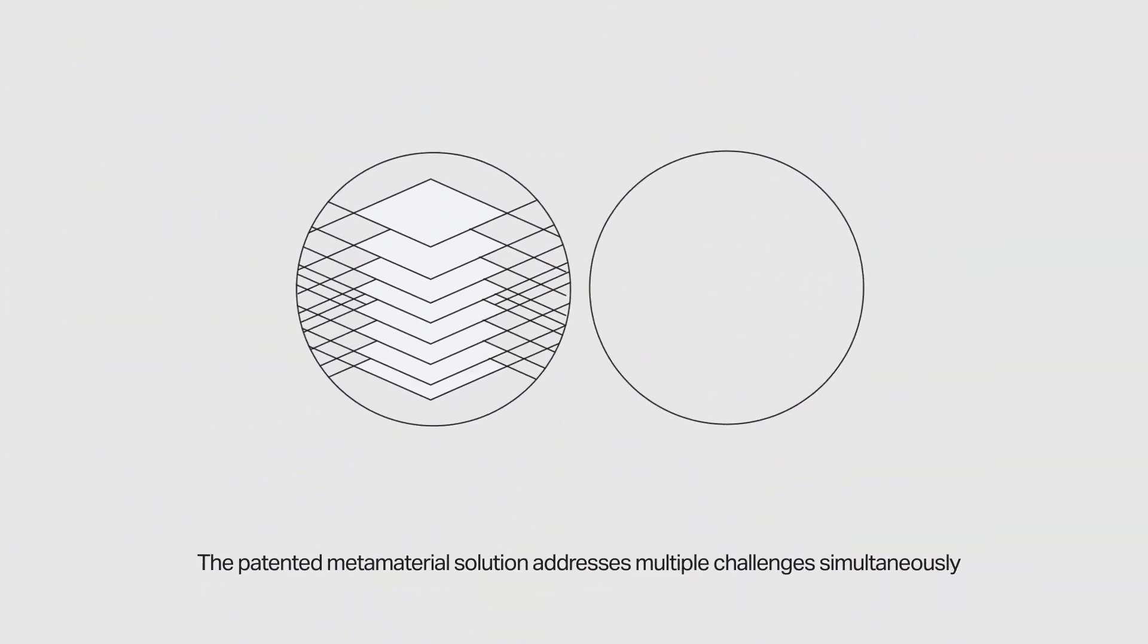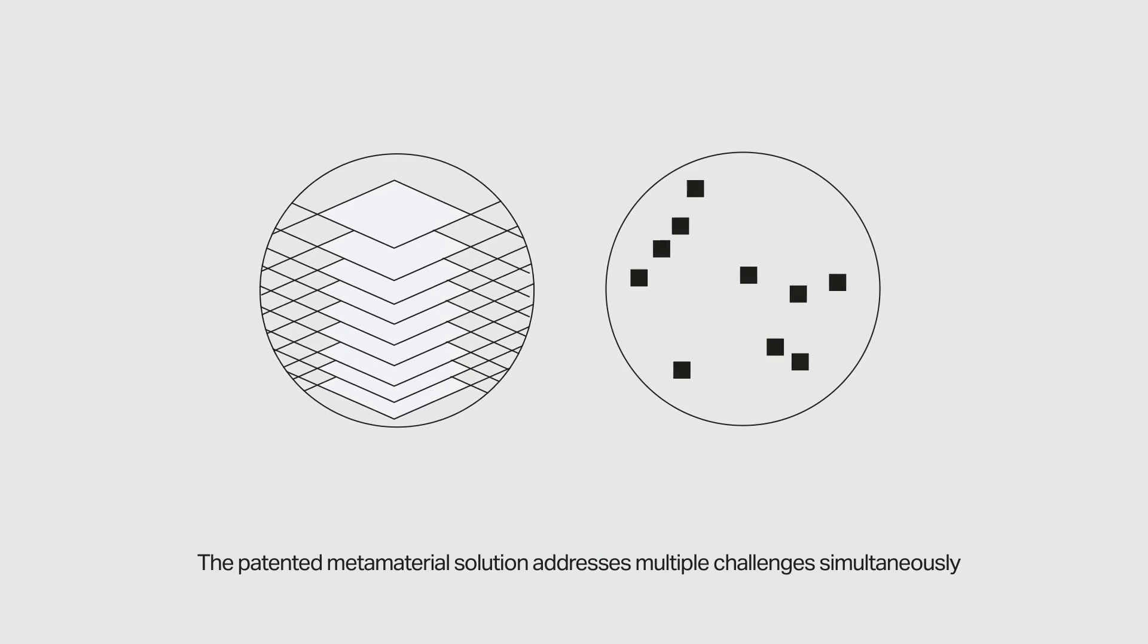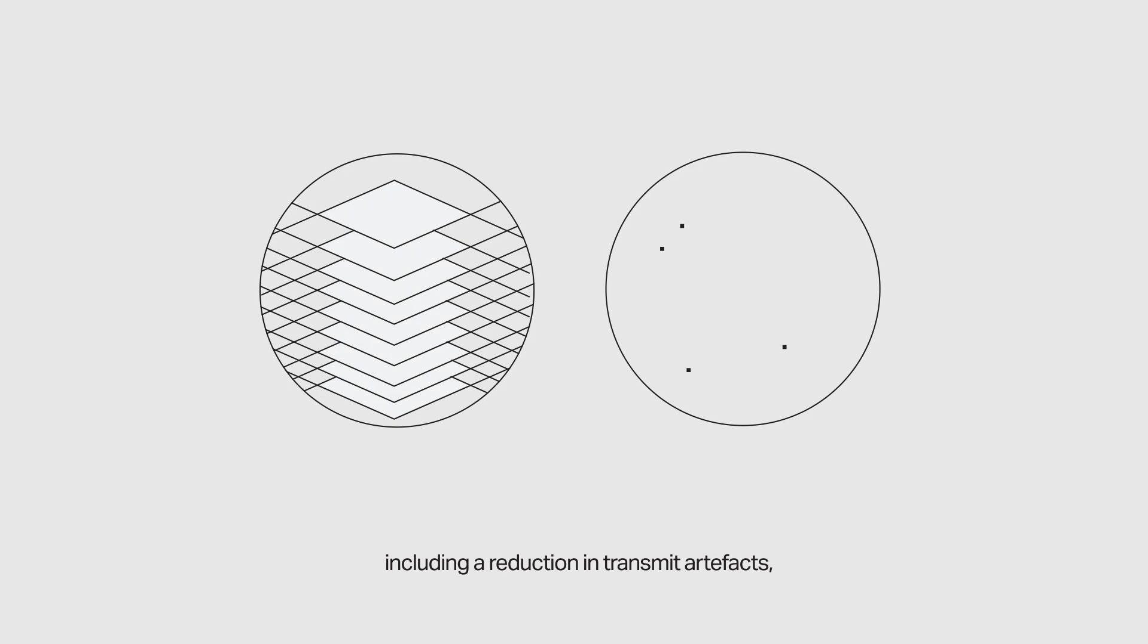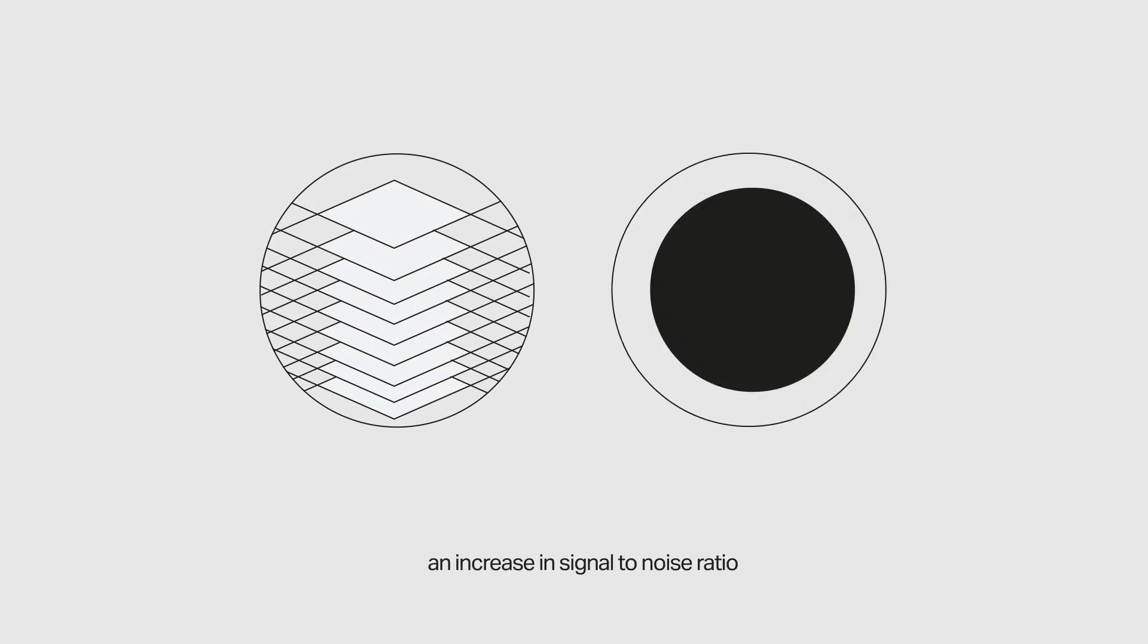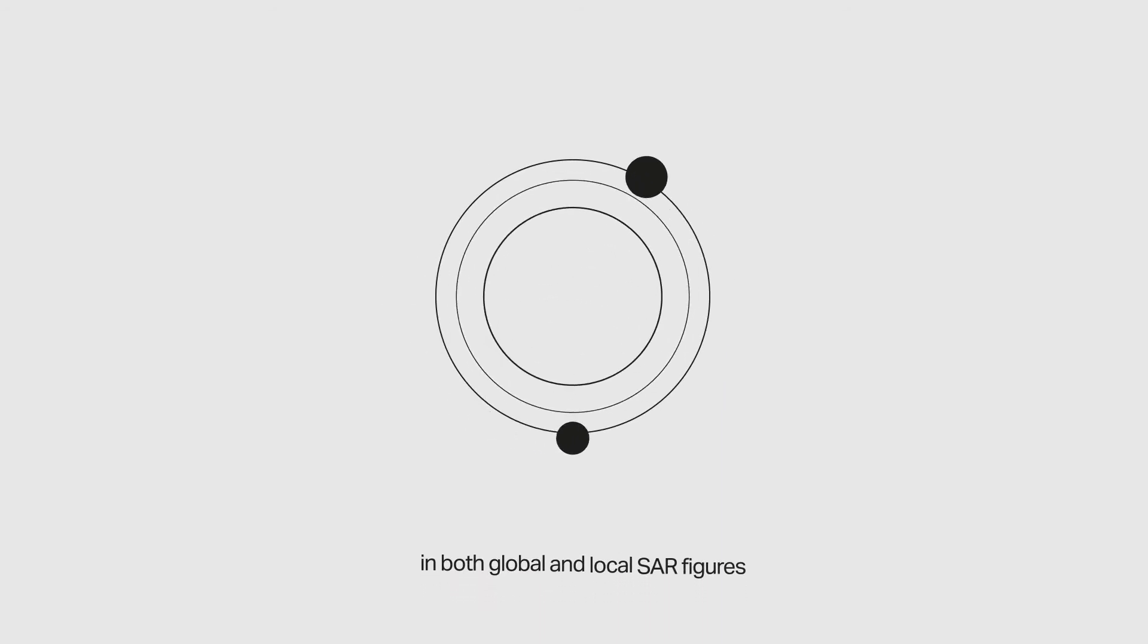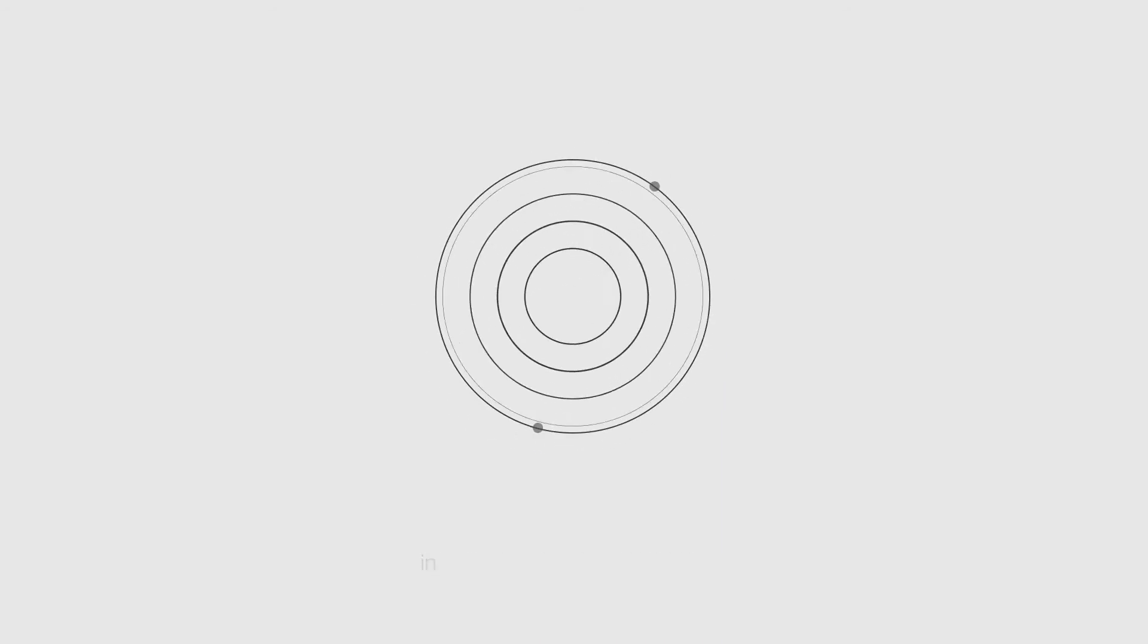The patented metamaterial solution addresses multiple challenges simultaneously, including a reduction in transmit artifacts, an increase in signal-to-noise ratio, and a guarantee of patient safety in both global and local SAR figures.